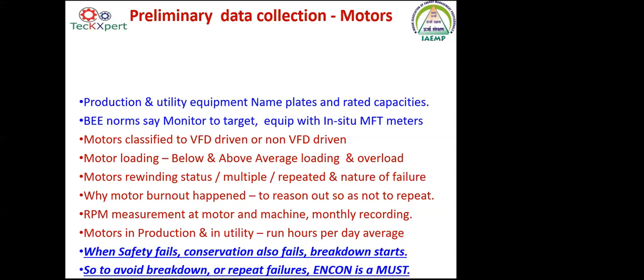Then comes the rewinding. Why is the motor getting burnt out? The root cause analysis has to be done by you as well. Whatever root cause analysis you have done, you have to discuss with the auditor to know why this failed and how it can be prevented from repeating. That also has to be discussed, because we don't want any other motor to be burnt out in your plant just because of obsolete bimetallic thermal overload relays. The concept has changed now. Thanks to electronic motor overload relays, which are based on negative phase sequence components of current sensing, there is foolproof protection for all your motors, especially your critical motors.